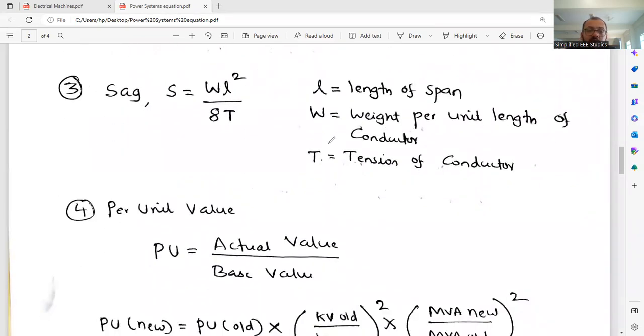Another important term is called sag. We have derived an expression: sag S is equal to WL square divided by 8T. L is the length of span, W is the weight per unit length of the conductor, and T is the tension of the conductor. That is very important. S is equal to WL square by 8T.